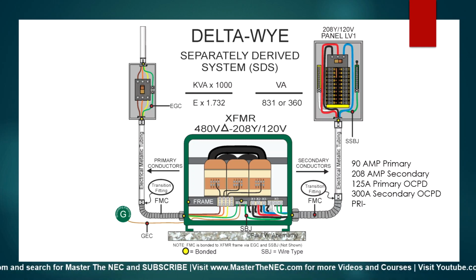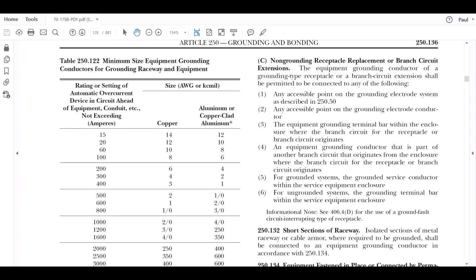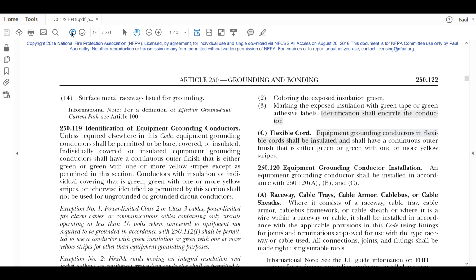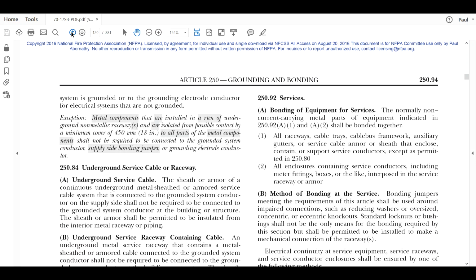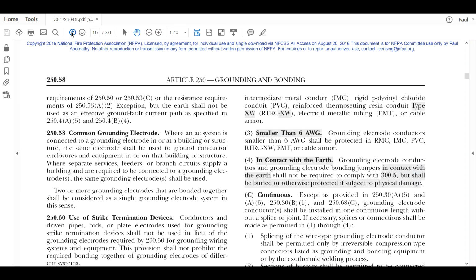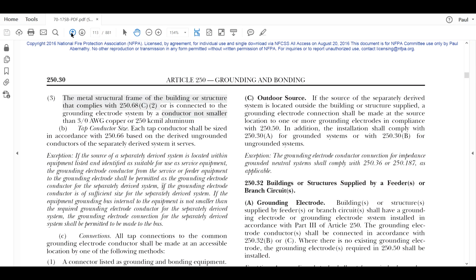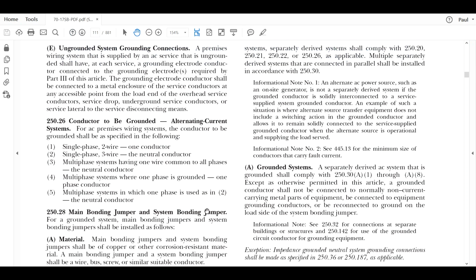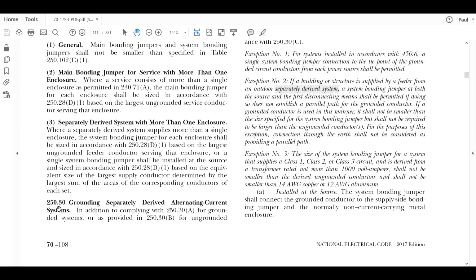So let's go look at what the code says first in 250.30. Now remember, 250.30 is an important place to remember because that's where you're going to get all the rules that have to do with system bonding jumper sizing, grounding electrode conductor sizing for separately derived systems, all those goodies. Now they're going to send you other places in the code, but that's where you want to go to have your foundation, if you will. All right, so here we are at 250.30. Remember, 250.30 is important because that's where you get all your grounding and all the aspects of separately derived systems.